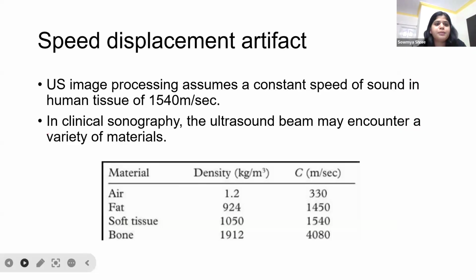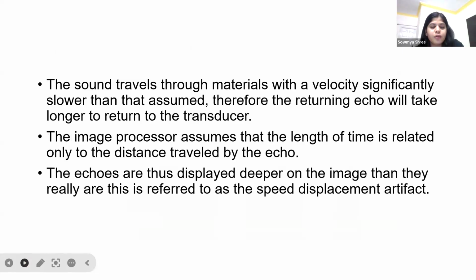The next artifact is speed displacement artifact. Ultrasound image processing assumes a constant speed of sound in human tissues of 1540 meters per second. But the ultrasound beam may encounter a variety of materials, and the speed varies in each of these materials. Because of this, the sound may travel through materials with a velocity significantly slower than that assumed. Therefore, the returning echo will take longer to return to the transducer.